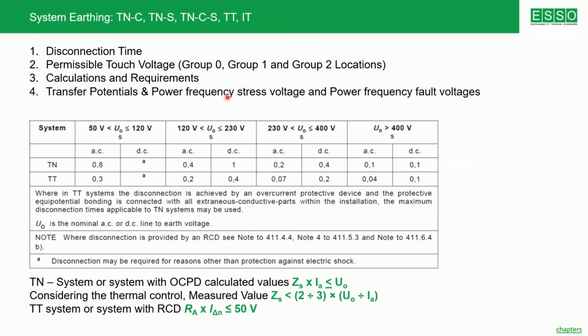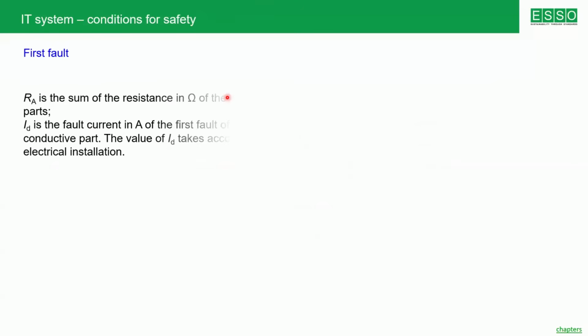This is a subject which tells you that in case of a fault on the high voltage side of a transformer, how much potentials and duration are allowed in the low voltage side of the transformer, because finally your equipment are capable of withstanding certain voltage for a certain time. Due to a fault, if the voltages are exceeding, then there will be failure.